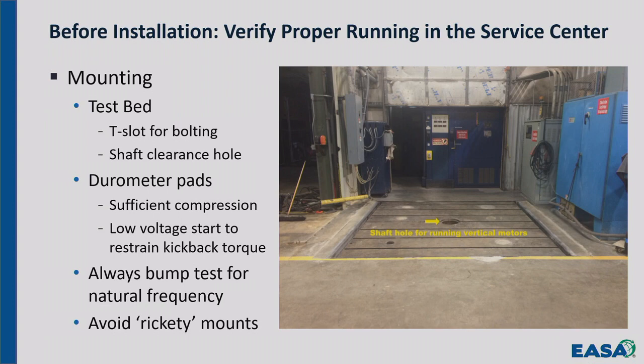So some thoughts there. If you bolt the motor down, you can do a bump test on it. How many people know what a bump test is? Okay, not everybody. If you're working on vertical machines, when somebody says bump test, you should automatically know what that is. You should have done it or have a technician who has done it. And it wouldn't hurt, if you've got a technician that's doing it for you, to have him show you what one of them is. If you talk to your customer about a bump test, the customer's looking, what the heck's a bump test? That doesn't sound like anything technical. And you should know what it is.